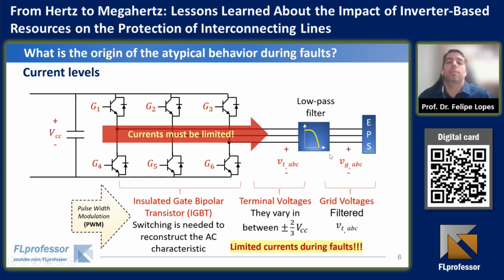But the main characteristic when we decided to analyze the inverters was related to the current levels. We read in several papers and books that currents must be limited here because otherwise this switch can present problems. So the limited currents during faults are explained. A lot of people think that the limited currents are only related to control schemes, but this is not completely true. Some IBRs have currents limited by the limiters that are applied to protect the switches.